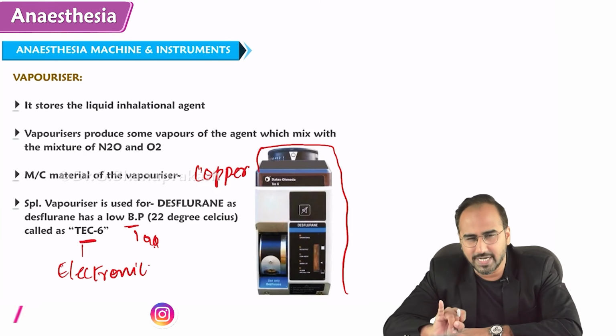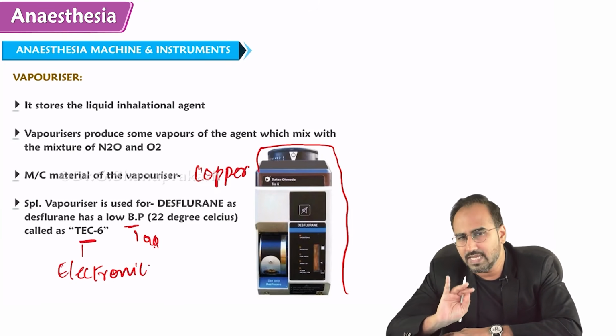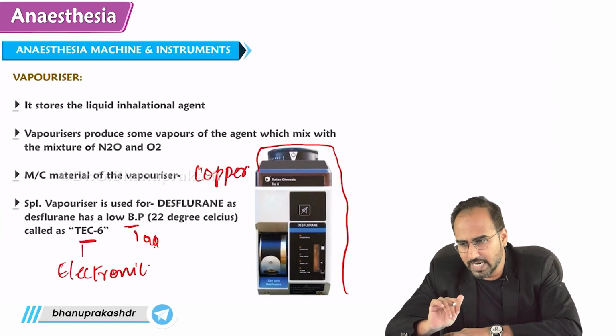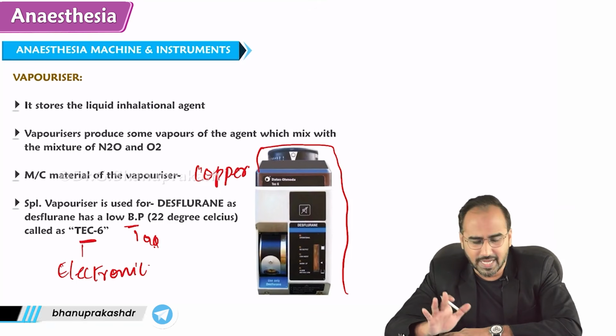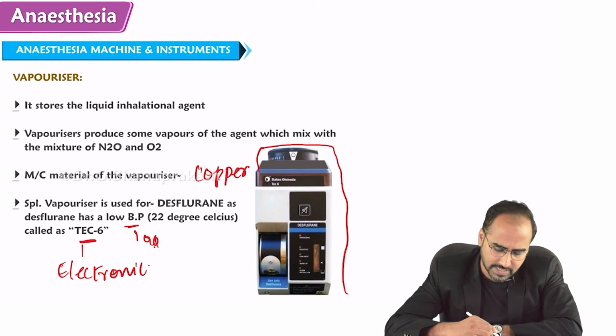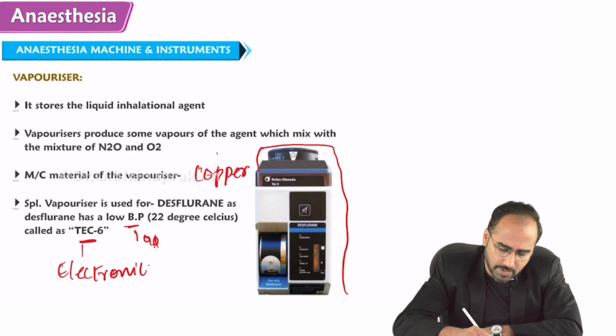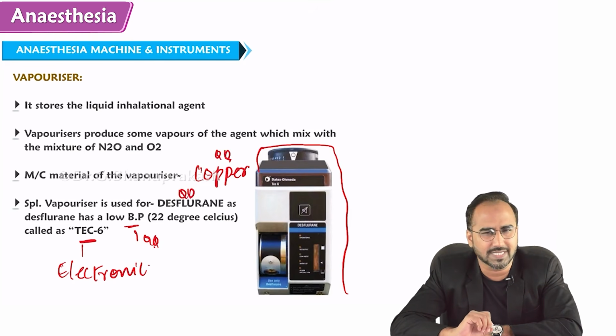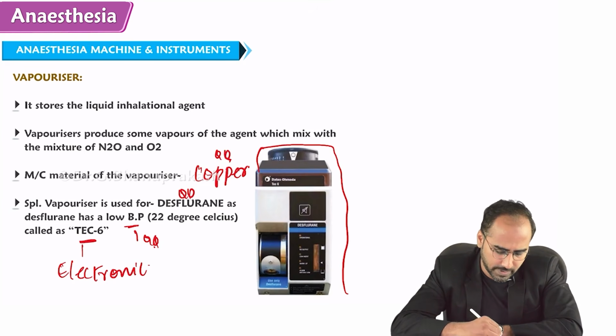We have discussed the cylinders, the yoke valve assembly, pin index system, emergency oxygen flush, and apart from emergency oxygen flush, the pressure regulating valve we have discussed, the flow meter we have discussed, and the vaporizer we have discussed. Okay? The most common material is important, and why desflurane requires a special vaporizer, that is also important. Why? Because it has a low boiling point, right?